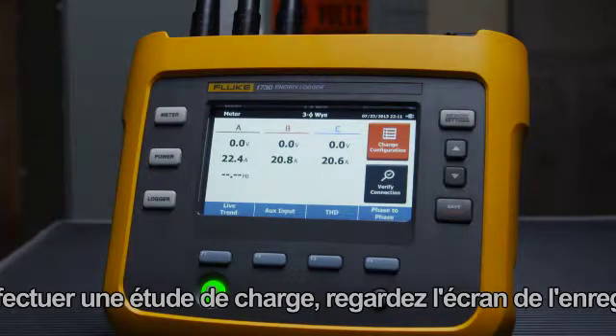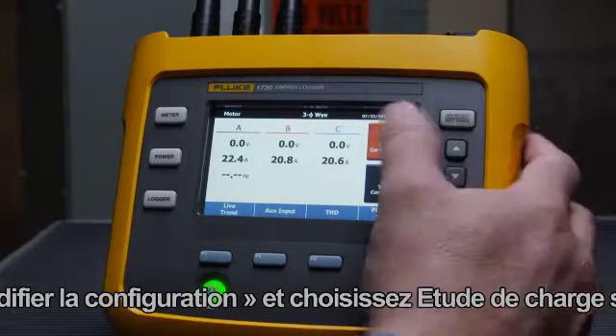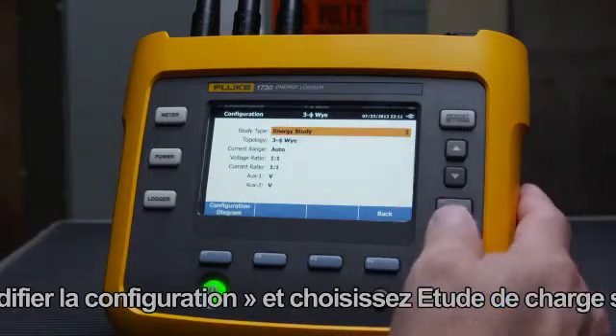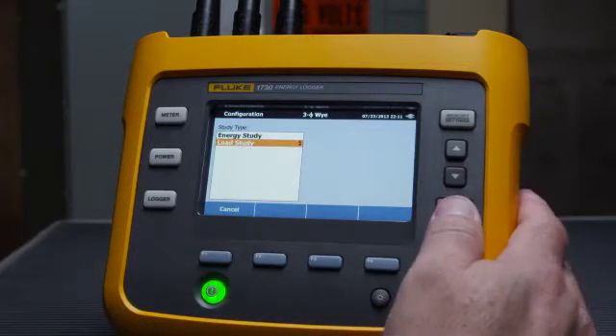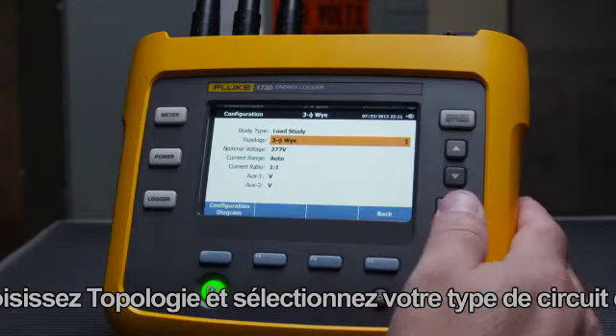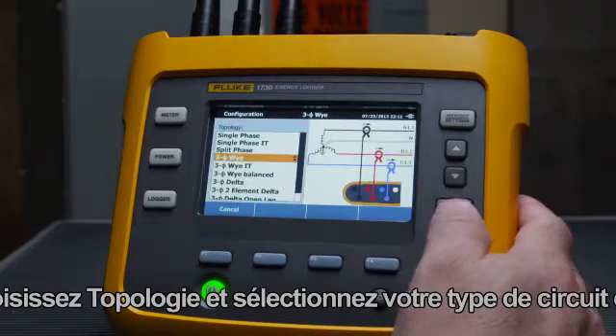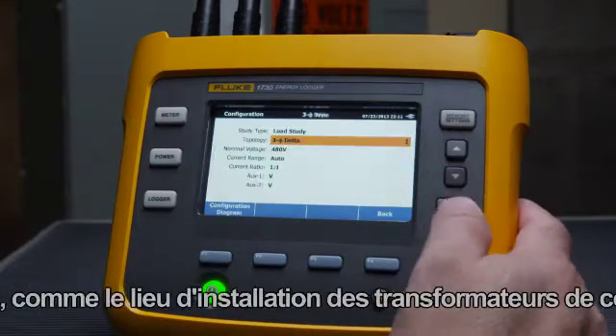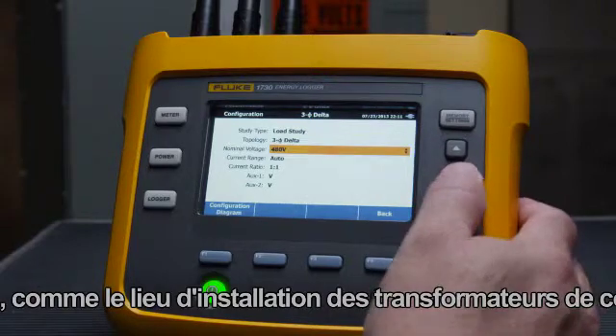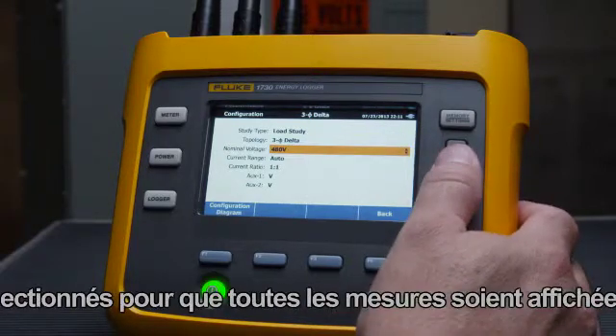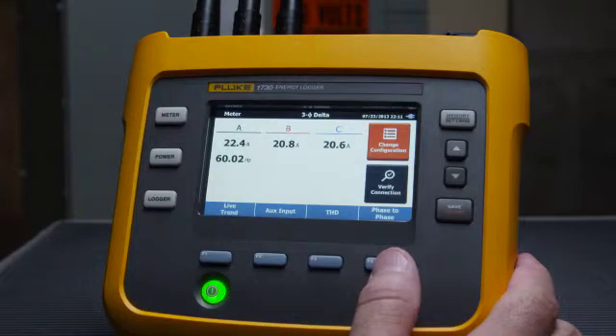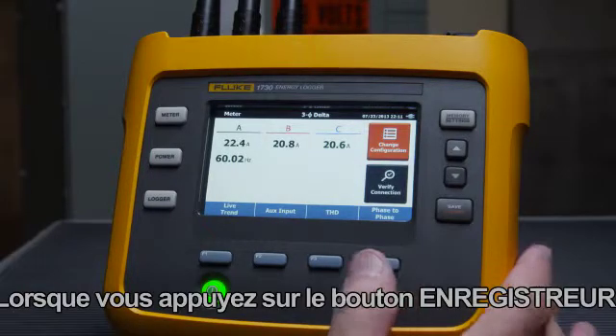To perform a load study, start in the meter screen, select Change Configuration, and choose Load Study under the study type. Now choose topology and select your circuit type from the list. Other settings, such as where the current and voltage transformers are installed, can be selected to ensure all measurements are shown correctly.